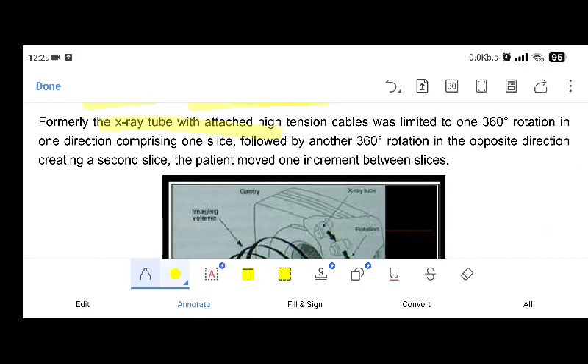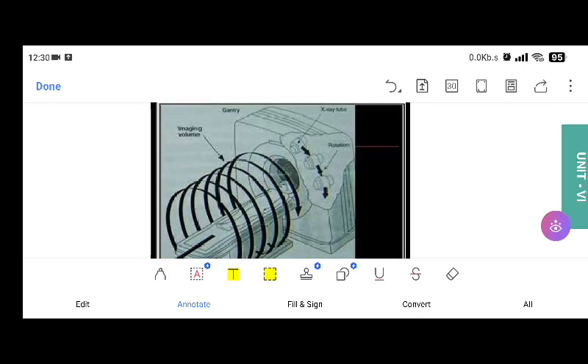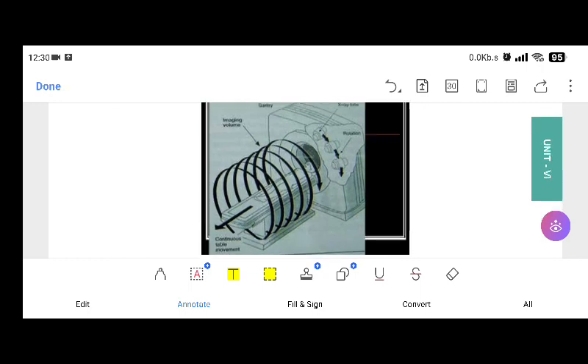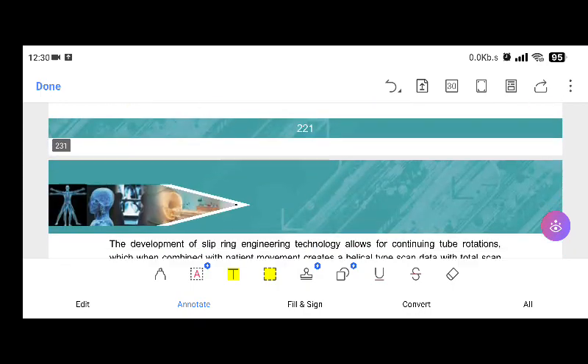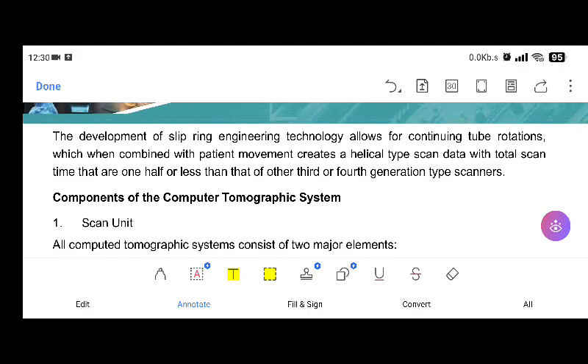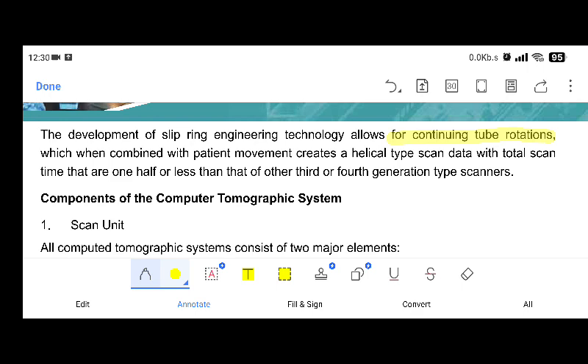Formerly, the X-ray tube with attached high tension cables was limited to one 360-degree rotation in one direction, comprising one slice, followed by another 360-degree rotation in the opposite direction, creating a second slice. The patient moved one increment between slices. So this is the helical CT. So, imaging volume and gantry X-ray tubes. The development of slip ring engineering technology allows for continuous tube rotation which, when combined with patient movement, creates a helical type of scan data, and the total scan time is one half or less than that of other third or fourth generation type scanners.